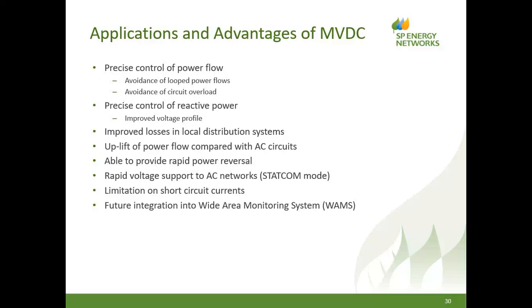I've mentioned the STATCOM mode. We can provide rapid voltage support to the AC network. So in the event of an AC network fault, we can automatically go into STATCOM mode. We can set the power to run to zero, so we don't feed the fault, and we could increase the STATCOM capability to maximum, or any other combination. The system studies will tell us what is the best control methodology here.